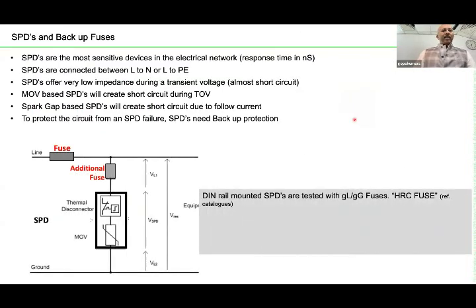Now, I have put a picture. First of all, from the line, you have an HRC fuse, then you have the SPD, then from the SPD there is a wire which is going to ground, the line and the ground. So the total voltage, as I said, the residual voltage, this voltage has to be lesser than the withstanding level of that particular device. The line length has to be as short as possible. Including the line length, in the sense, the wire including the fuse has to be as short as possible.